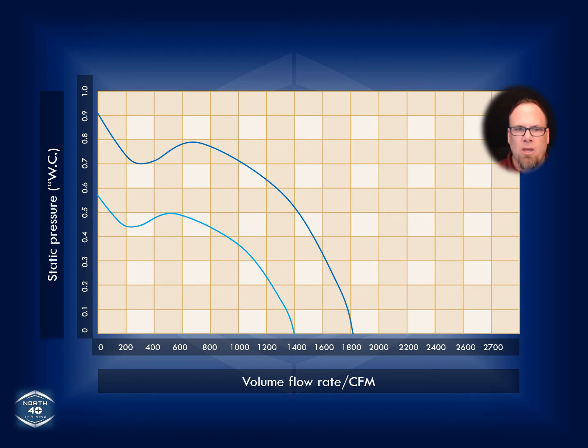We know most manufacturers want you to set up an air conditioning system to operate at 400 CFM per ton on most, some of them are at 350 CFM per ton. But if you look at the 400 CFM per ton, what that's telling you is a 1-ton unit would use 400 CFMs. A 2-ton unit's 800. A 3-ton unit is 1200 CFM. And you're trying to set it up for that value. Okay, so how do you figure out where that actually leads?